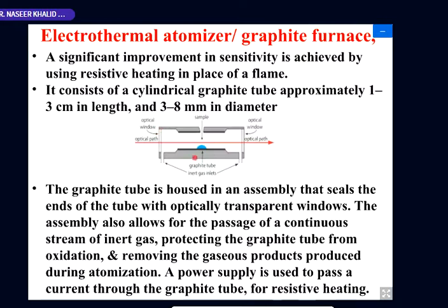Okay. Now, the graphite tube is there. Here the hollow lamp is there. Here the burner is there, or if we are replacing this burner with this, it is called an electrothermal atomizer because it is electrically heated. Electrically heated means electrothermal, I mean the atomization process takes place by means of electricity. And then there is a monochromator, a detector, an amplifier, and then the recorder. So this will be the block diagram of atomic absorption.